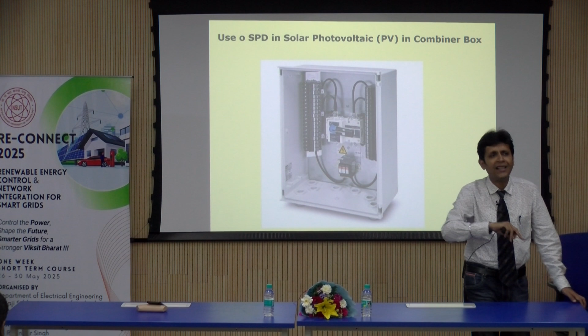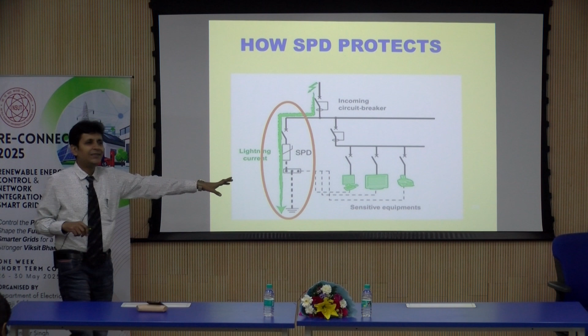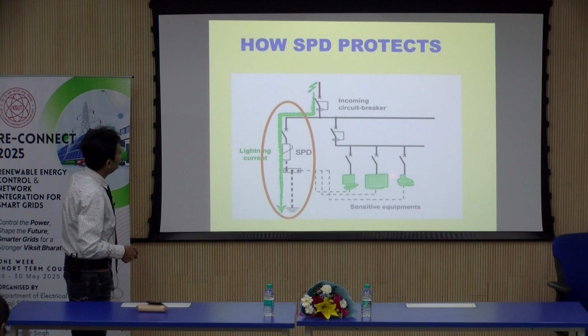And when I say SPD, it is of 3 types: type 1, type 2 and type 3. When I say type 1, type 2, type 3, next one. This is how SPD helps you to protect the equipment you are using in your system. At the time of fault, that works on the principle of equipotential. For that particular duration, SPD will create equipotential between the gadgets and the earth.